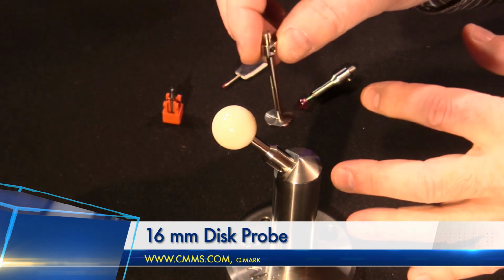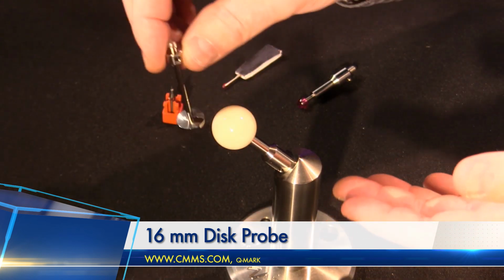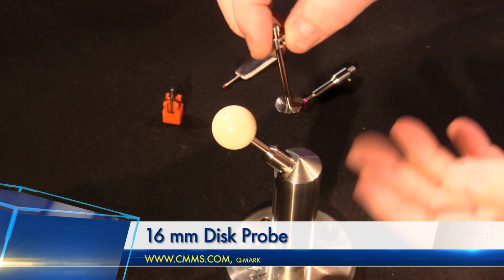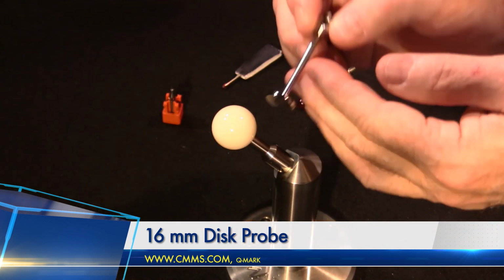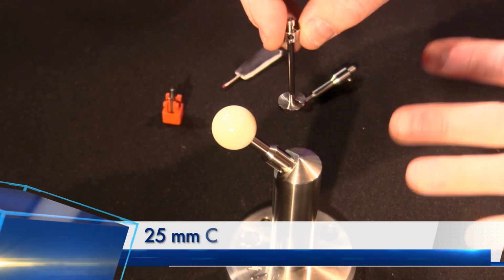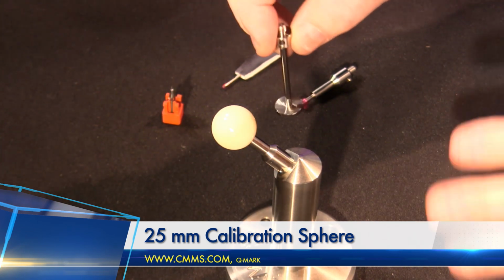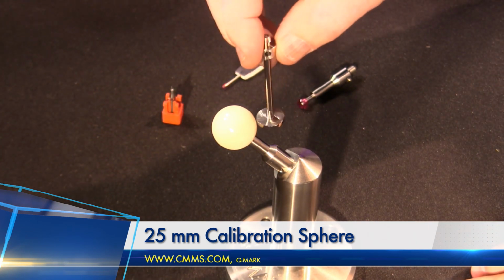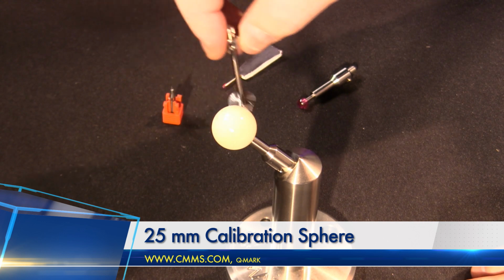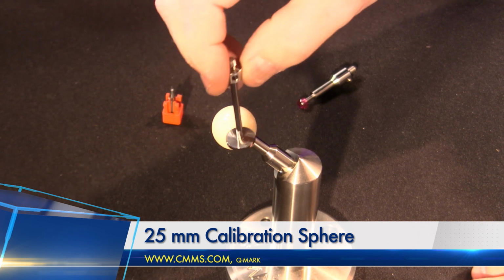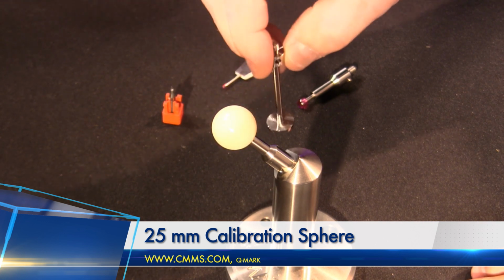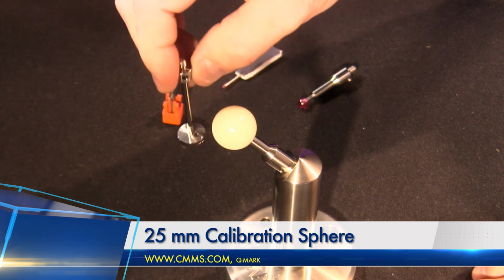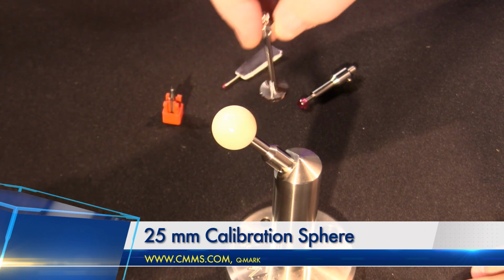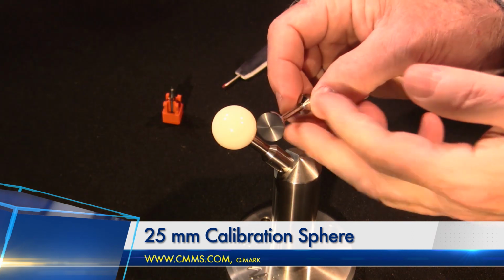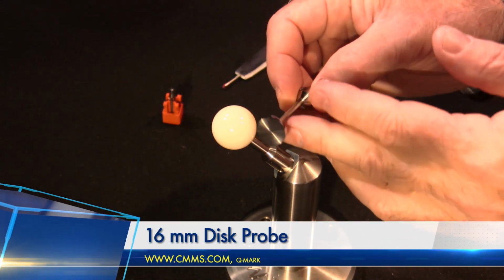Now, where I'm going to be touching this probe, you can get that information, the actual distances, from QMark. It depends on the size of the sphere and the size of the probe, but the process is always the same. You're going to take 12 measurements, 4 at the equator, 4 at a predetermined distance above the equator, and 4 at a predetermined distance below the equator, so 12 total. Then you're going to take that data to qualify or calibrate your disc probe.